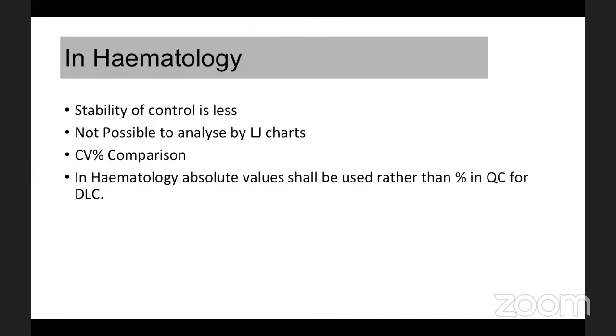What we can do instead is calculate the CV percent for different lots and compare that CV percent. If CV for lot A is 2%, CV for lot B is 2.1%, and CV for lot C is 2.3%, the CVs are comparable, meaning our precision is okay.